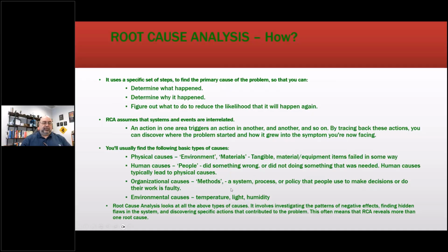So when we get into a root cause failure analysis like that, it's like, okay, what idiot made that decision, right? Well, why? And then you get to, okay, safety department made that decision. Nobody from the reliability and maintenance department was involved in that decision-making process. Why did that occur? And then you go on, you're like, well, OSHA requires you to do an analysis, and you have to have all the stakeholders involved. So there was a problem with their process.